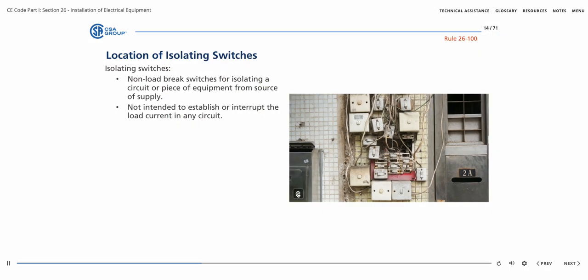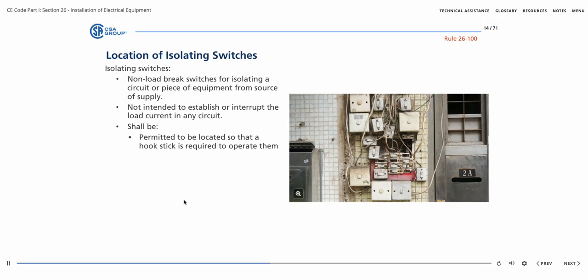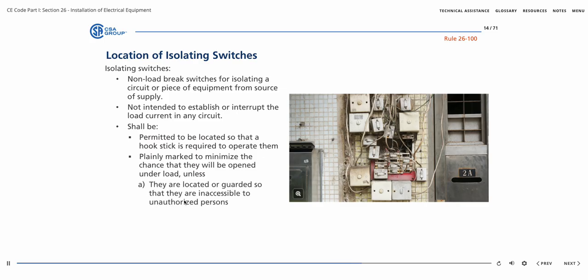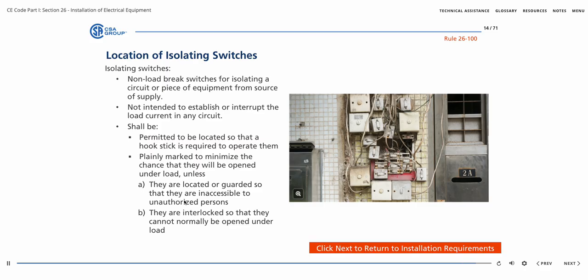Rule 26-100 permits an isolating switch to be located so that a hook stick is required to operate it. It must be plainly marked to minimize the chance that it will be operated under load, unless it is located or guarded so it is inaccessible to unauthorized persons, or it is interlocked so it cannot normally be opened under load.